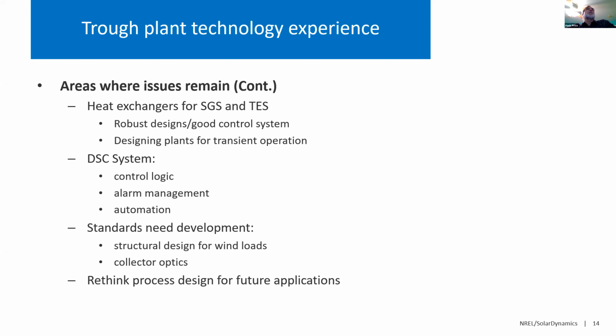There have also been some questions on quality control of supply. These are very big heat exchangers, so quality control during manufacturing is also very important. The DCS, or distributed control system, is the control system for the power plant. Oftentimes the control system is not designed from an integrated standpoint, so there are definitely improvements that can be made. Often the control systems look at individual systems like the turbine or the steam generator separately, or the solar field separately, rather than how to control the overall plant most effectively. So there's still room for improvement in the control logic.